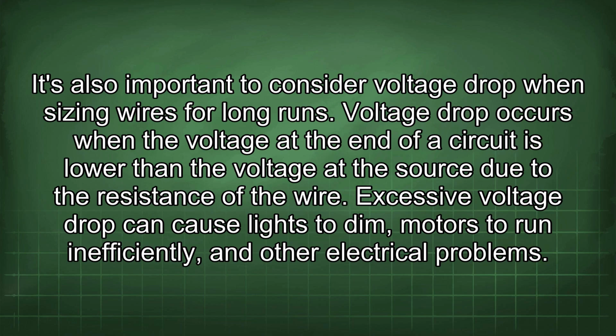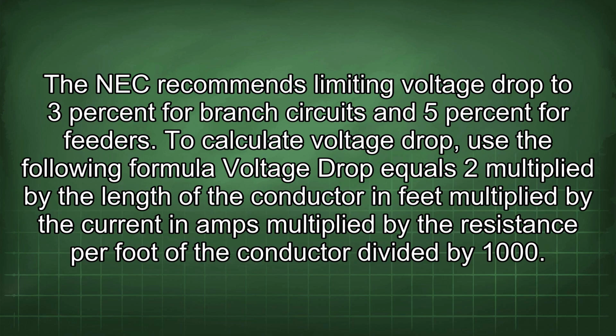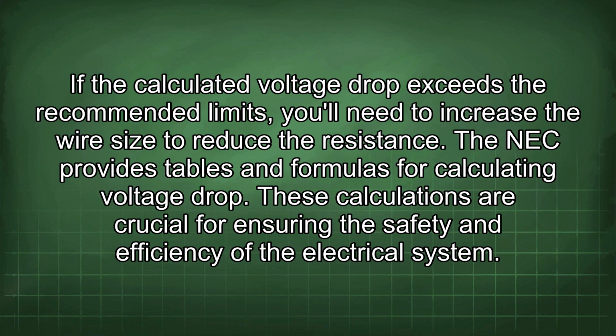Excessive voltage drop can cause lights to dim, motors to run inefficiently, and other electrical problems. The NEC recommends limiting voltage drop to 3% for branch circuits and 5% for feeders. To calculate voltage drop, use the following formula: voltage drop equals 2 multiplied by the length of the conductor in feet multiplied by the current in amps multiplied by the resistance per foot of the conductor divided by 1000. If the calculated voltage drop exceeds the recommended limits, you'll need to increase the wire size to reduce the resistance. The NEC provides tables and formulas for calculating voltage drop. These calculations are crucial for ensuring the safety and efficiency of the electrical system.